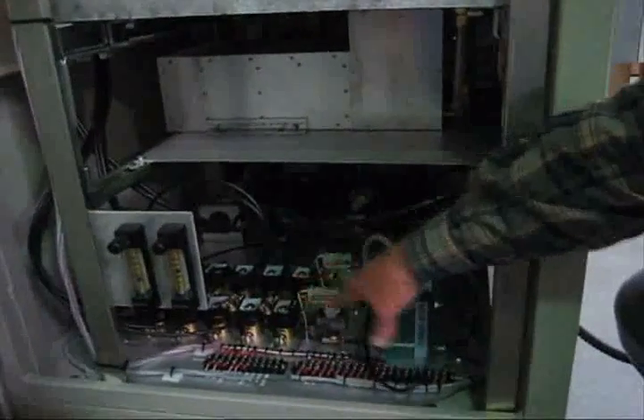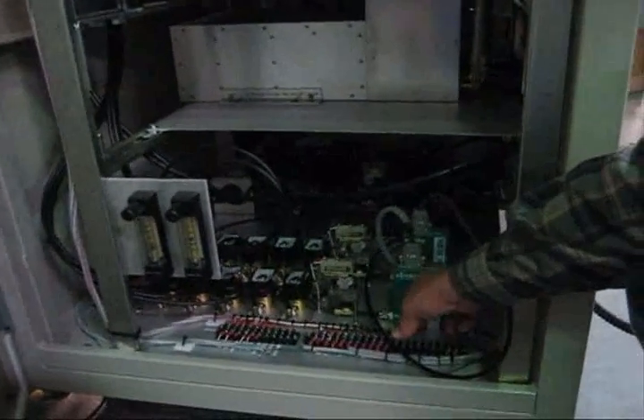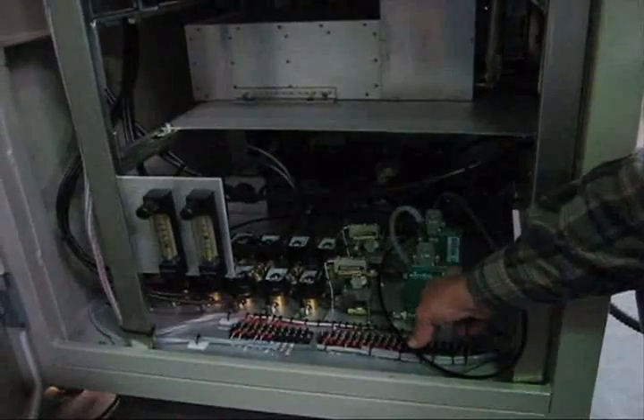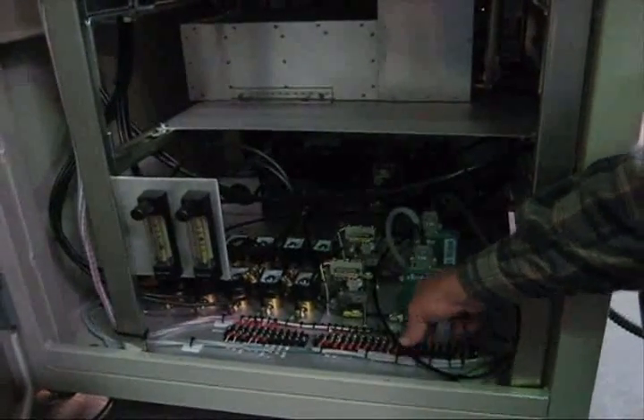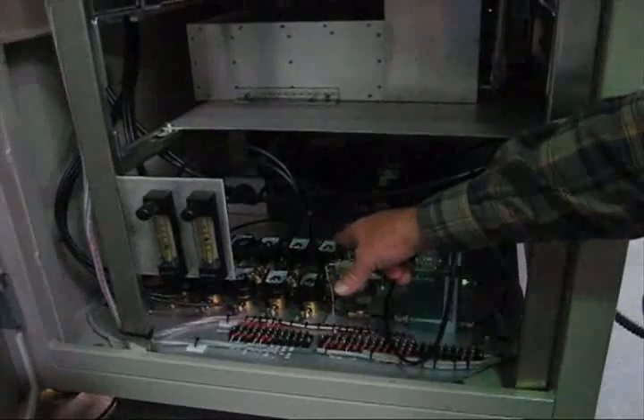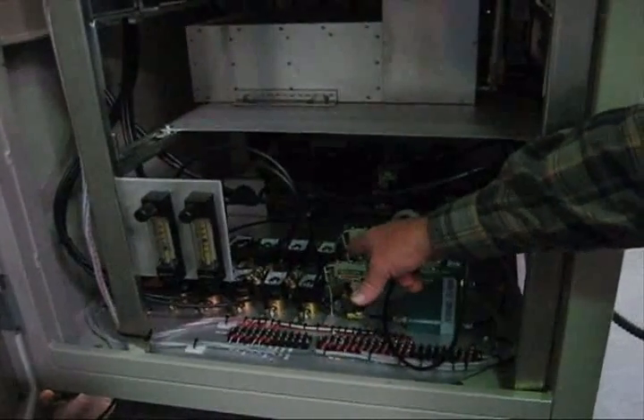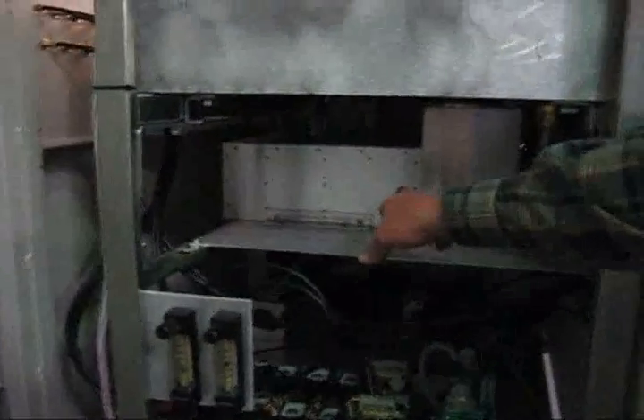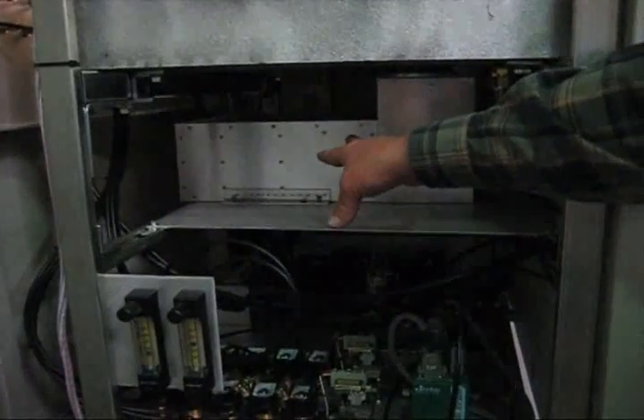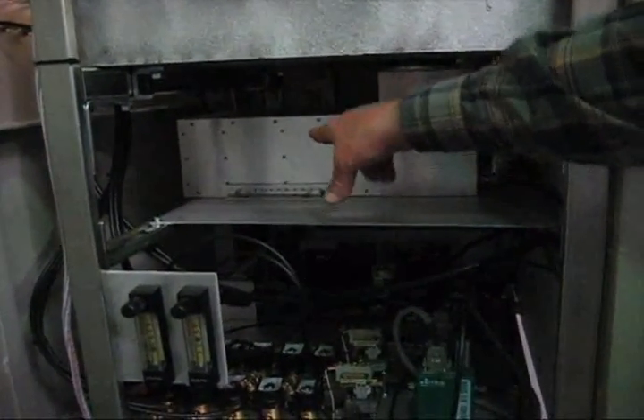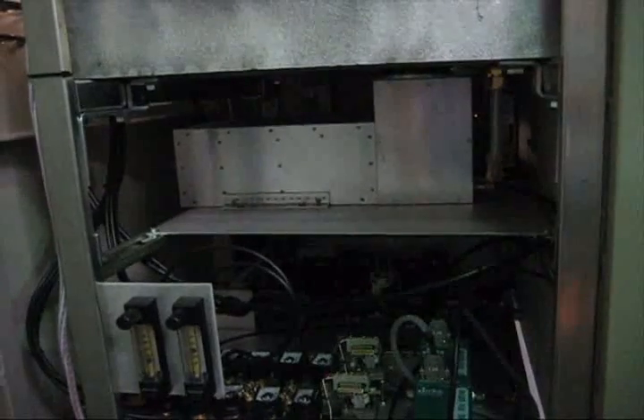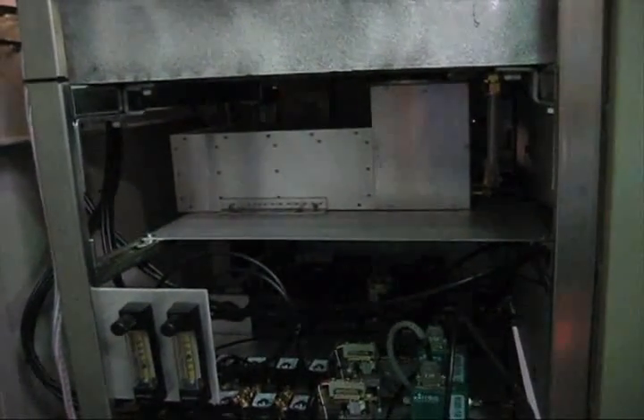Let's go around to the far side here and look at the gas board. Down here is the gas board. This is what we call a steering matrix, where we have two mass flow controllers on this unit. You can have three or four if you want. But with these two mass flow controllers, we have the ability to steer five different gases through it with the software, just like you saw on the screen. Here's the matching network for this unit. The generator always wants to see a 50 ohm load, and that's what the matching network does. It adjusts the load to the generator to make it happy.